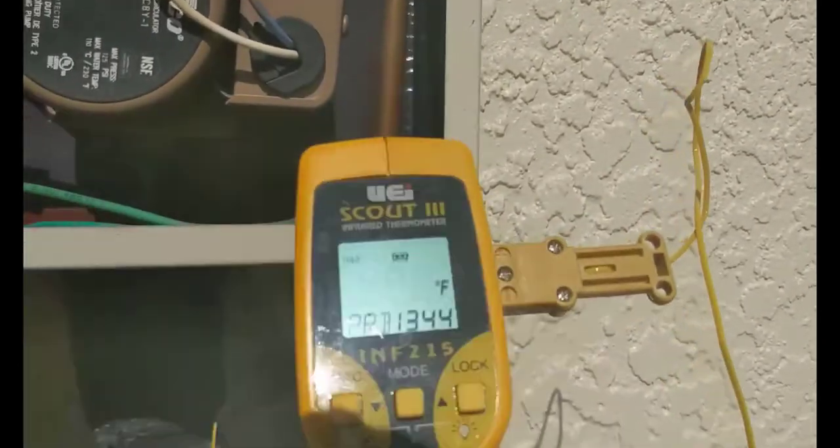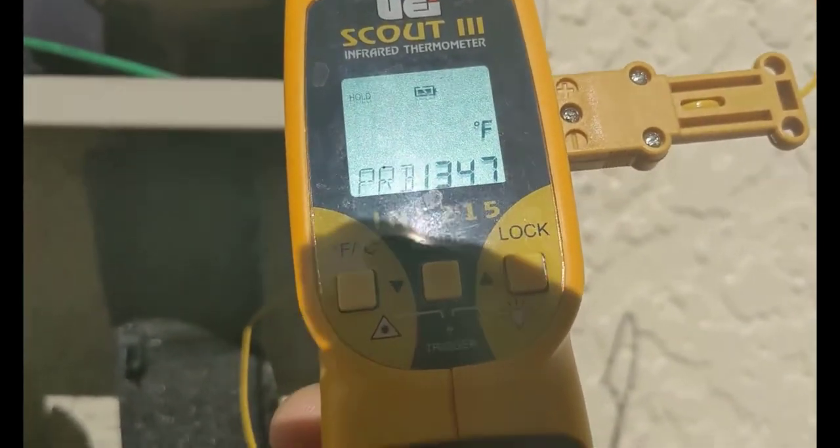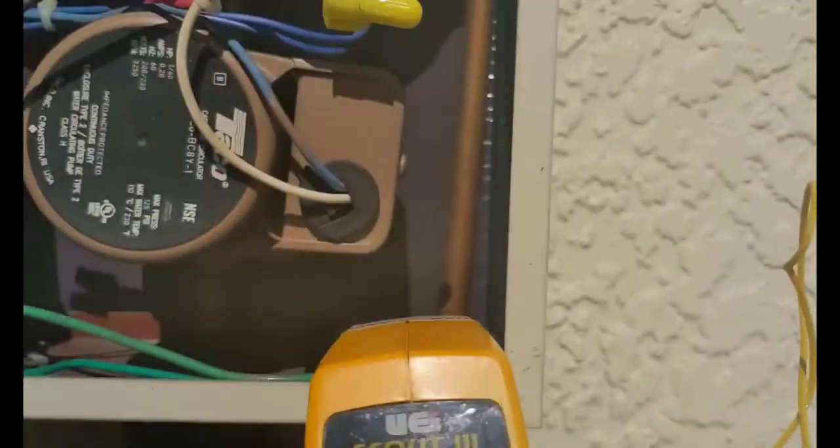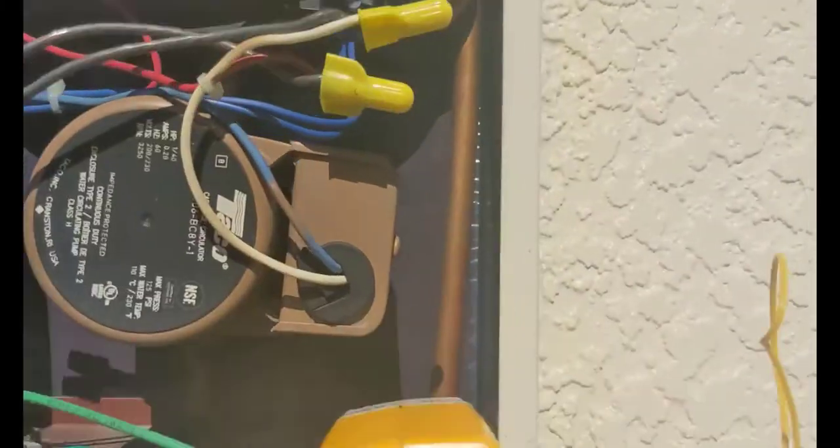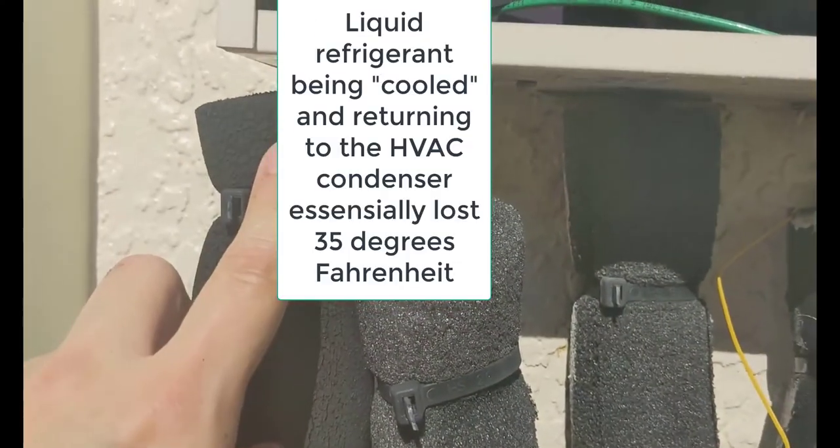So what we are measuring now, if you look behind there, okay right there, is the gas coming back to the air conditioning unit after it's already gone through the heat exchanger. So it goes through the heat exchanger and as you can see even though it's hot in the 130s it's a lot cooler than the way the gas left the system.